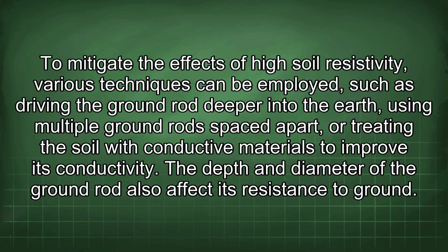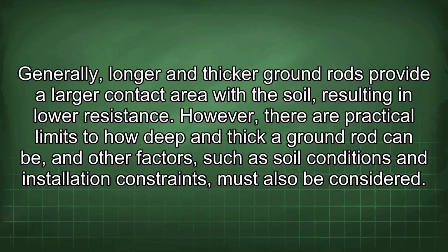The depth and diameter of the ground rod also affect its resistance to ground. Generally, longer and thicker ground rods provide a larger contact area with the soil, resulting in lower resistance. However, there are practical limits to how deep and thick a ground rod can be, and other factors, such as soil conditions and installation constraints, must also be considered.